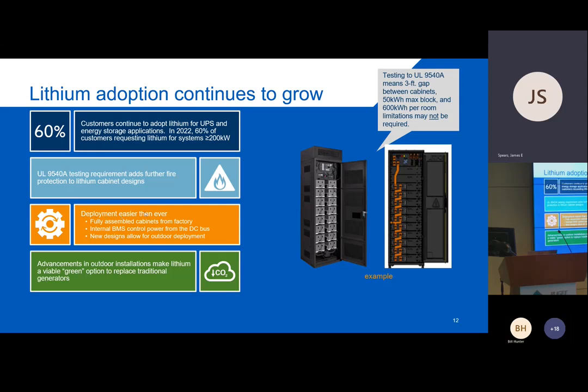Deployment is easier than it was. With some of the cabinets in the early days, not only did you need to connect positive and negative DC to the UPS by power cables, you also had to provide AC power, either 480 volts or 208 volts, derived from the output of the UPS, so that power was present even when the utility was off, when the UPS is running on those batteries.